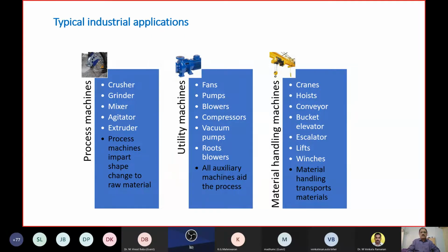So it's also important for us to take a look at three classifications when it comes to typical industrial applications with motors. I divide them into three. Process machines, applications involving process machines, for example crusher, grinder, mixer, agitator, extruder, where shape change takes place of the raw material. Whereas in the case of utility machines or auxiliary machines, like fans, pumps, blowers, compressors, vacuum pumps, and roots blowers, you saw approximately 66% of the total motor applications are in this area of utility machines, where the machines aid manufacturing and don't necessarily get involved directly in the shape change. So auxiliary machines are mostly centrifugal in nature. Important for us to understand this as we progress.